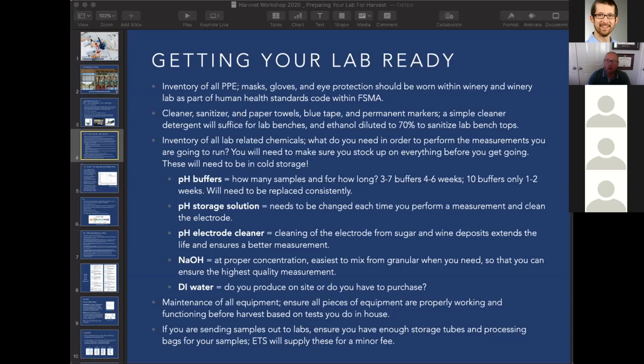And then DI water, do you have enough DI water? You need to be using DI water for your rinsing. You need to be using DI water for your TAs. And for the calibration of your refractometer. So you want to make sure that you have enough DI water on site. And if you are producing it, is your equipment working properly? Or if you're purchasing it, make sure that you have enough. You may want to stock up. You want to definitely maintain those pieces of equipment and make sure they're working properly before harvest. I'm going to talk a bit about maintenance in a little bit.